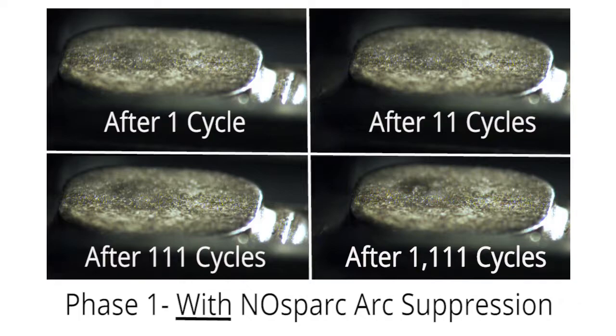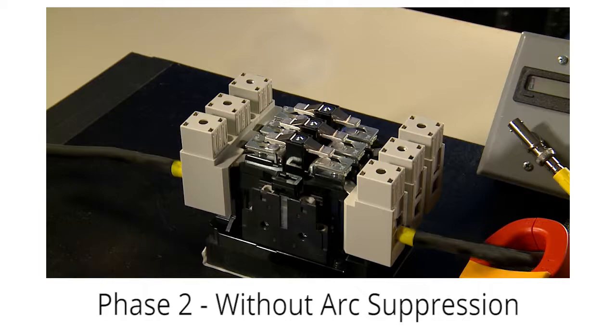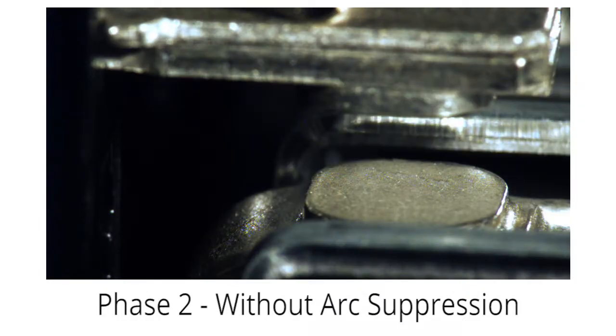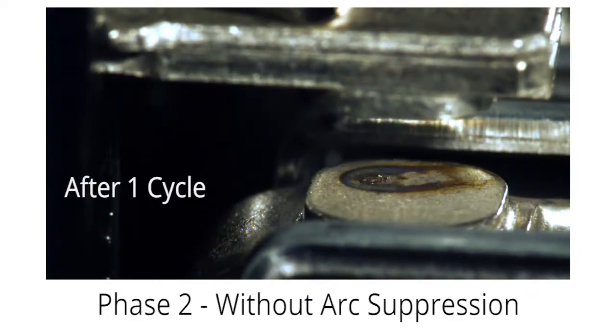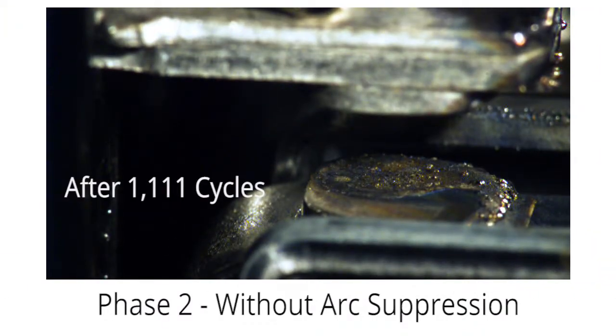We captured video of the contact cycles, and after each waypoint we shot close-up images of the contact surfaces. In phase two, we removed the NOsparc arc suppressor and connected the Hobart arc welder directly into the opposite unused leg of the power contactor. We left the arc welder at the same 235-amp setting and ran the contactor through the same number of operations — 1 cycle, plus 10, plus 100, plus 1,000 additional cycles — for a total of 1,111 cycles, this time without arc suppression.